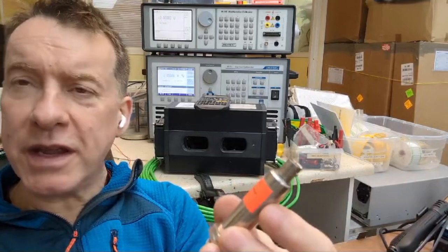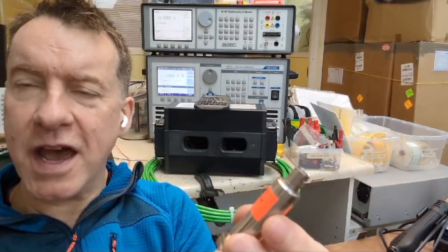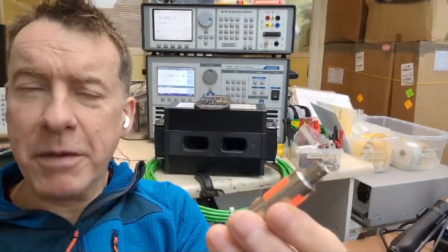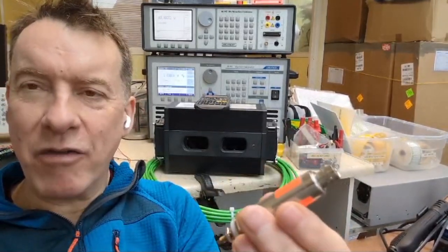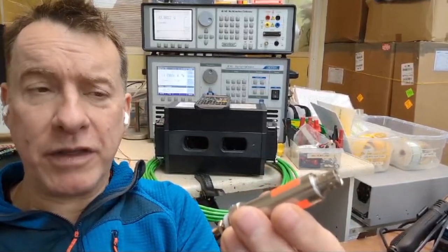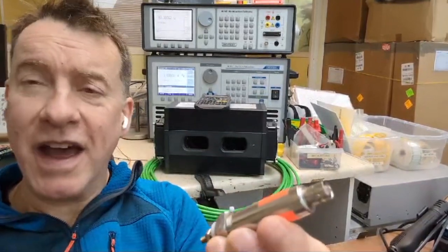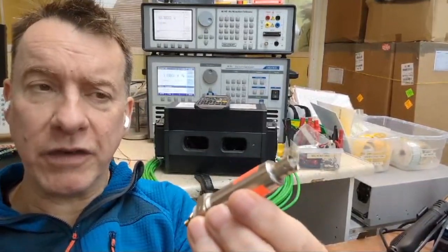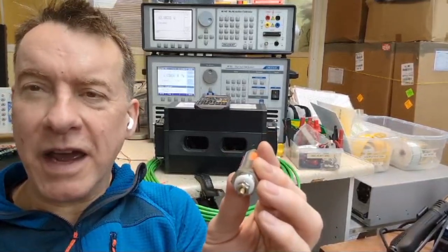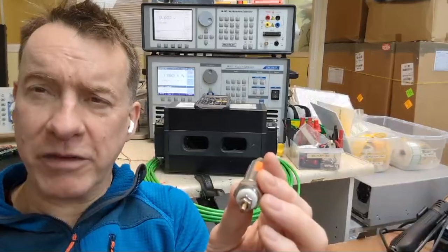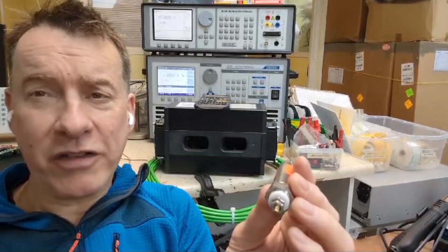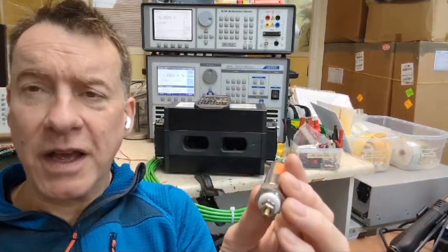And the accuracy, we can get accuracies in terms of the resistance to about 0.1%. So they're pretty accurate, but more to the point, they retain that relationship. The voltage current relationship is pretty flat over a wide bandwidth into hundreds of megahertz and down to DC. So a very useful device, particularly if you look at today's power electronics where so many engineers are looking at rise and fall times of switching devices, because clearly that's where lots of the power is lost during that transition.